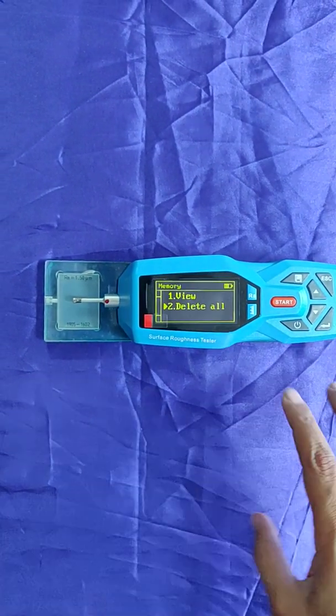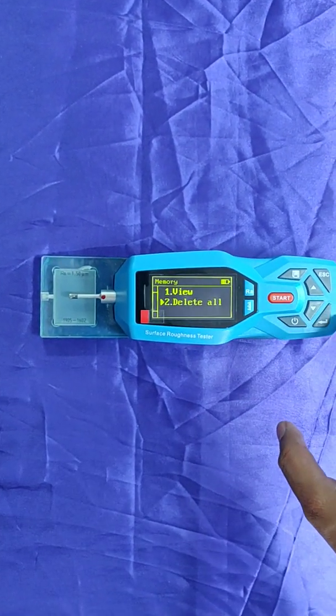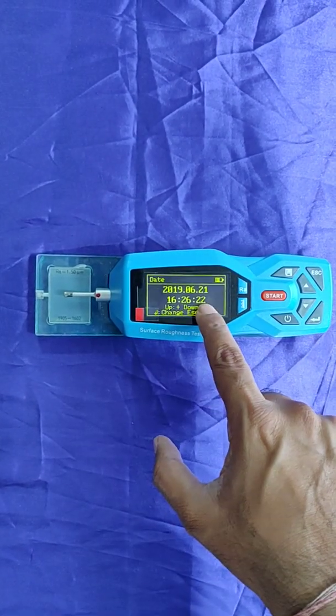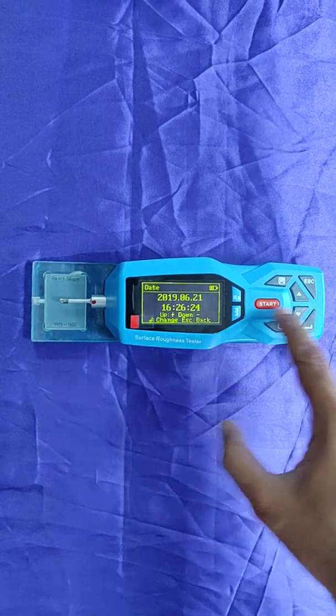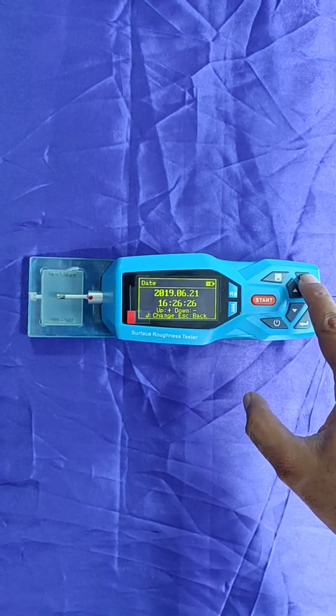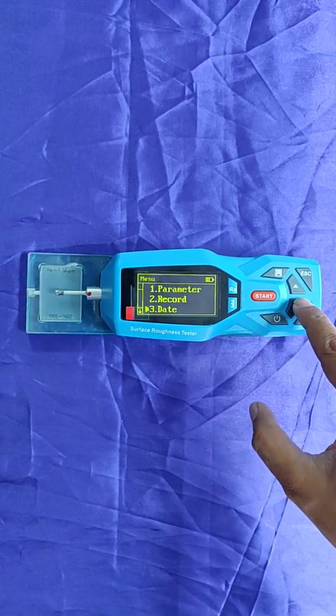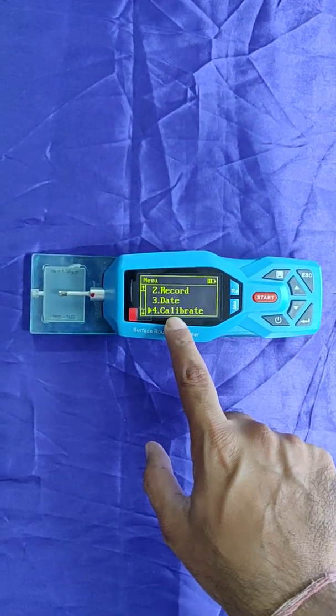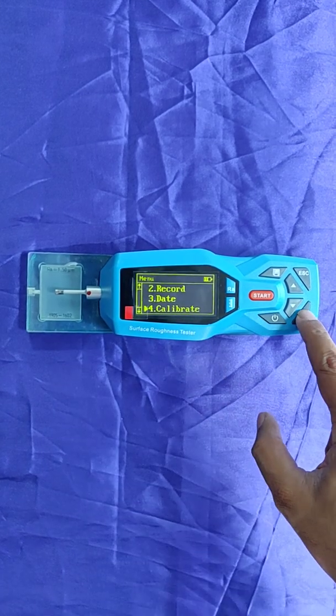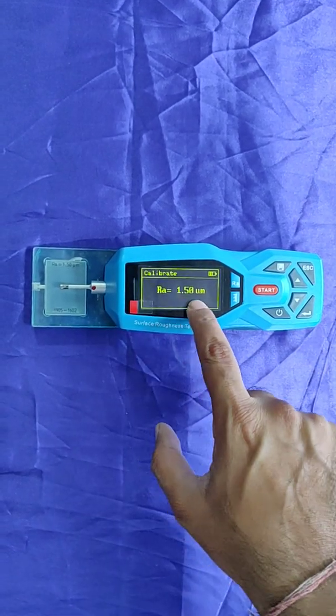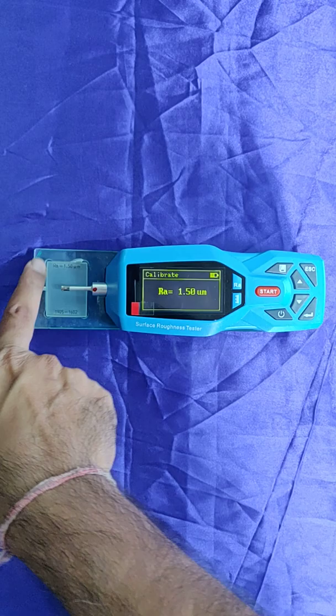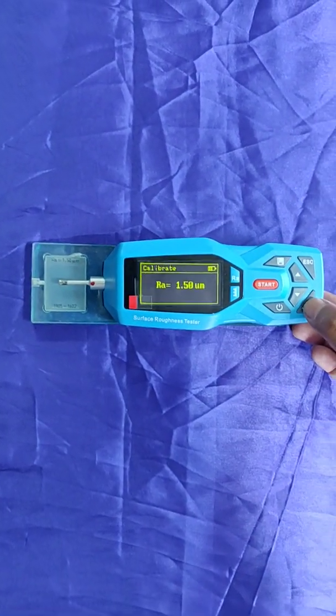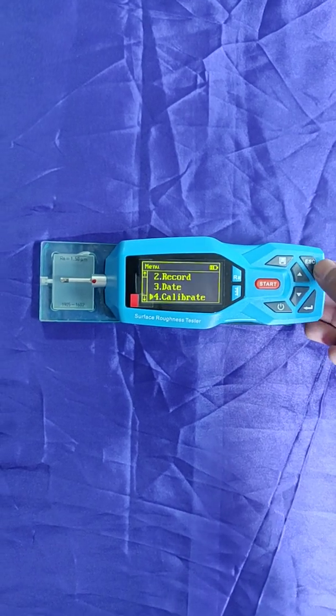Now escape. Date we have already set in - 21st June 2019. Go back. Calibrate - very important. The most important thing we need to understand is calibrate. So enter. It is already mentioned 1.50 microns, which is the same here. So we are calibrating this instrument on 1.5.